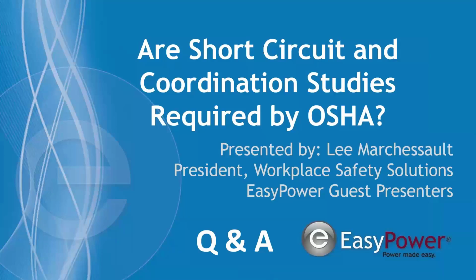So if you don't do that assessment to determine your fault current and clearing time, that's another reason to do this study. But if you're going to do that level of study to use the tables, you might as well do an engineering study, because once you get the data for the short circuit and coordination study, you got all the data you need for the arc flash study. So that's just the better way to go, is just get an arc flash study done, then you've got it all done. And it helps give you ammunition of why the arc flash study needs to be done. It's also OSHA compliance with coordination and short circuit. I know I drifted there. I'm sorry about that. No, it was a good discussion.